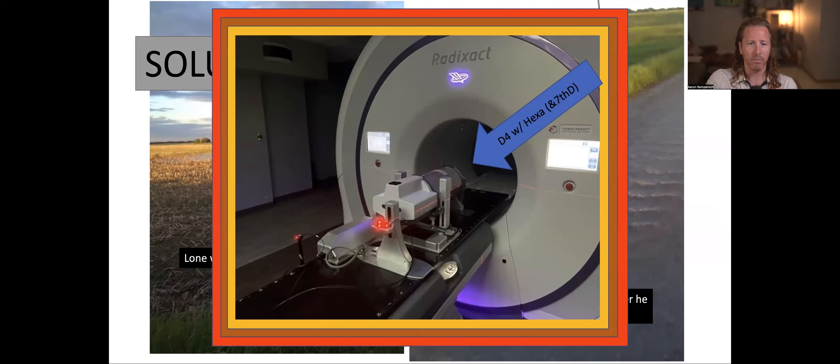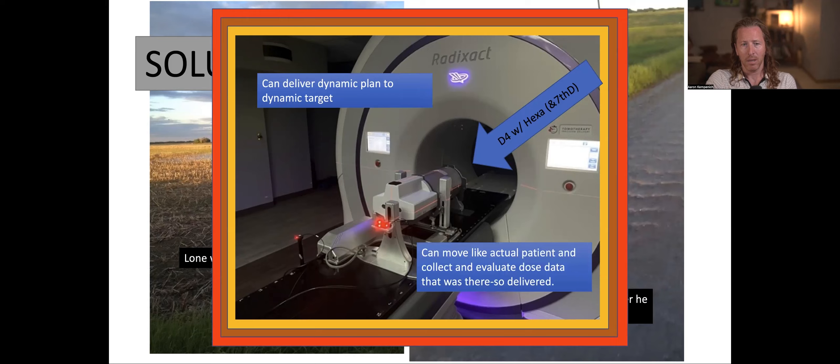You can get as close to in vivo measurements on a real patient that moves inside with this. So I can deliver a dynamic plan to a dynamic target — Radixact says it can do it. The Hexamotion Delta IV says it can move like an actual patient and collect and evaluate dose data that was delivered. So I'm going to run some tests, run some plans for you all, and we're going to see that I can do it.